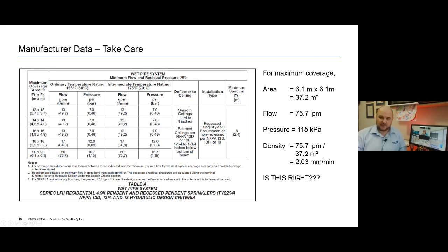Unfortunately, this is not the way we should be designing systems. You'll see down here at point 3 within the data sheet, I really want to highlight this because it's really important. Here we have this clause right under the table, part 3 for NFPA 13 residential applications. This isn't part R or D, this is NFPA 13 high-rise residential applications. The greater of 0.1 gallons per minute per square foot, or 4 millimeters per minute, over the design area, or the flow in accordance with this criteria must be used.